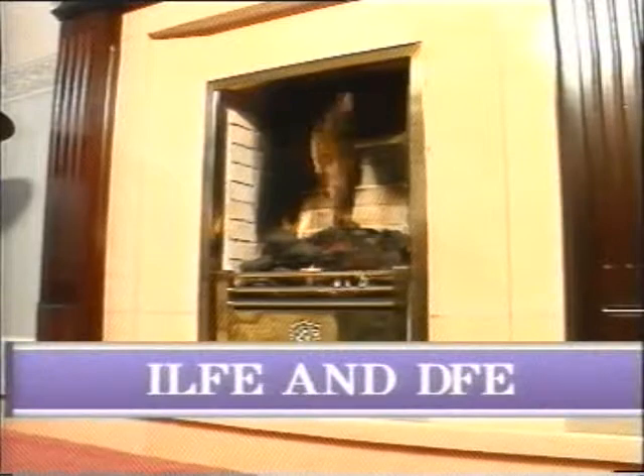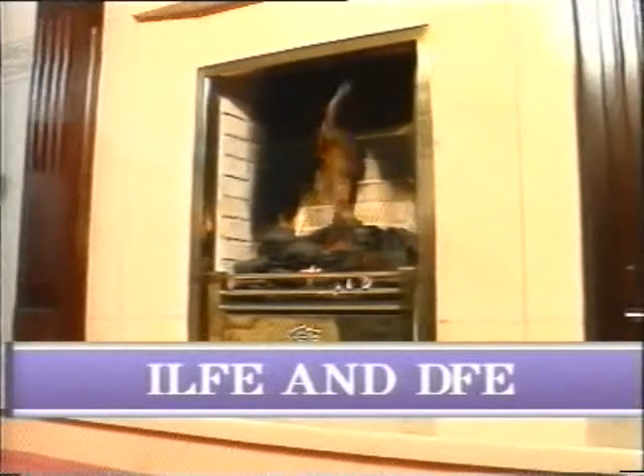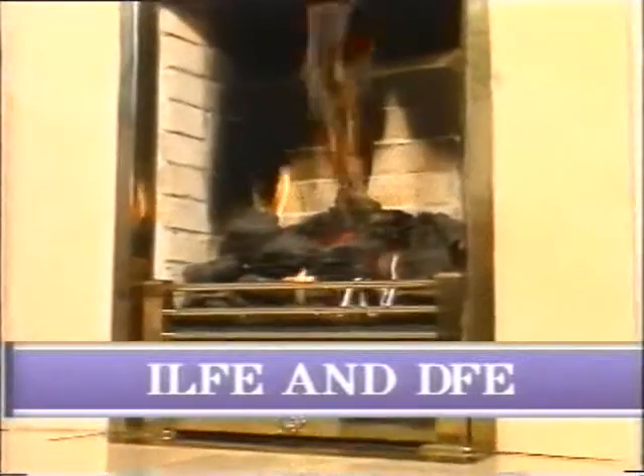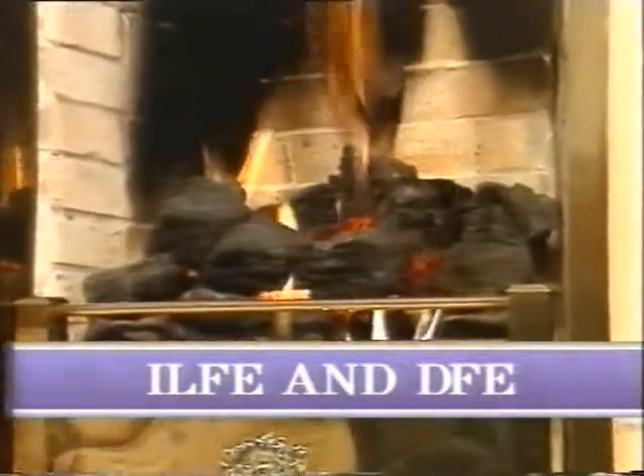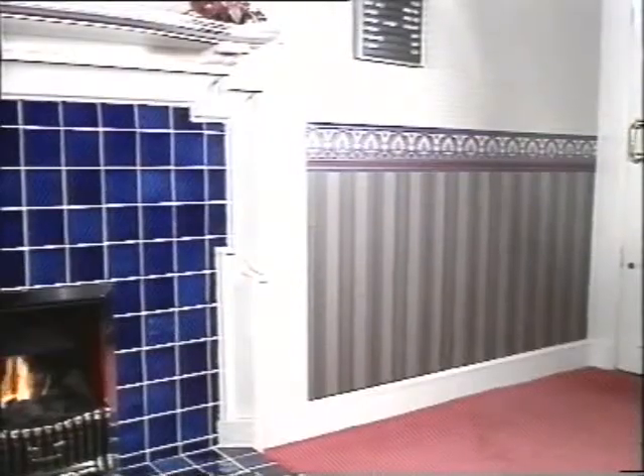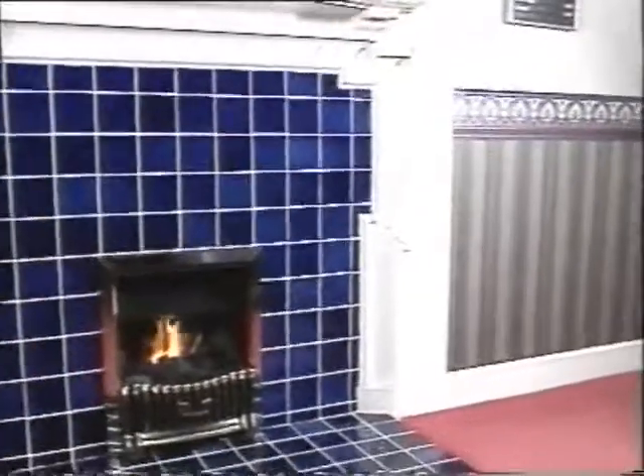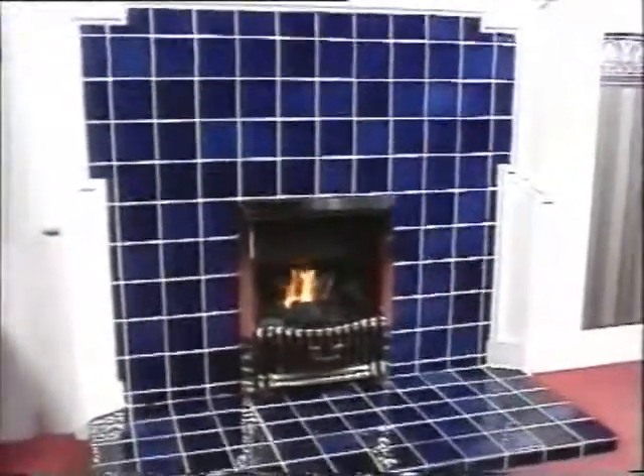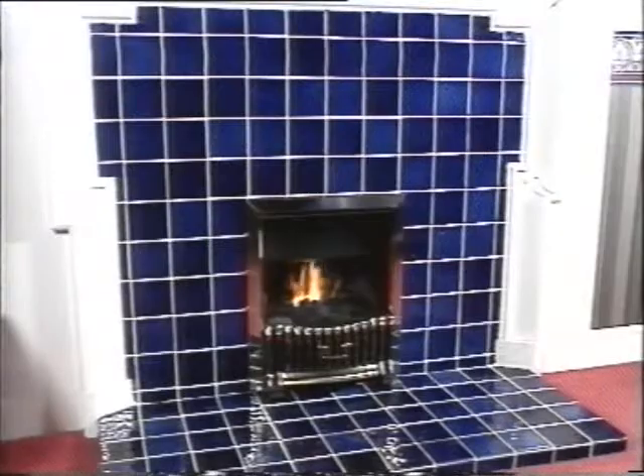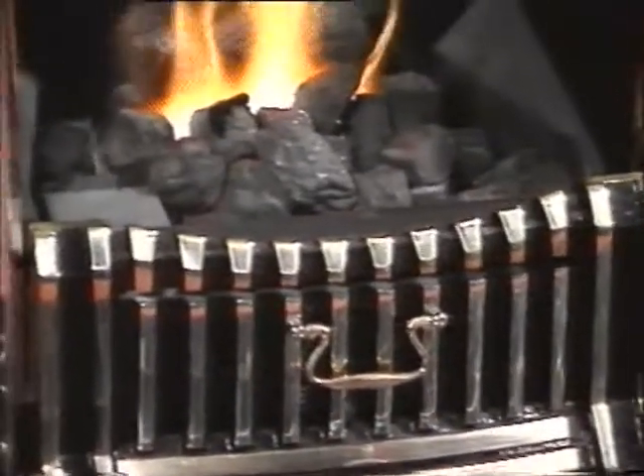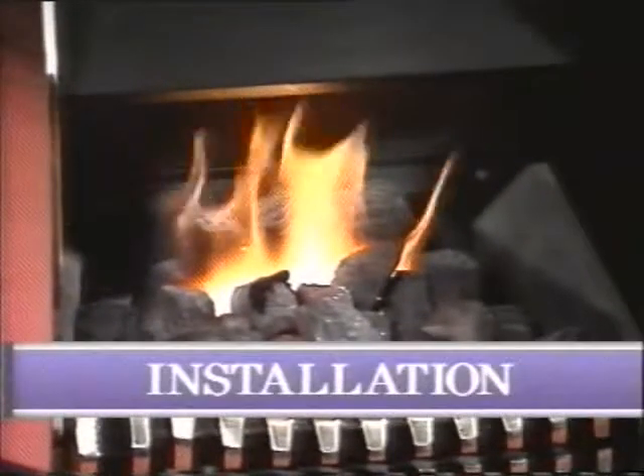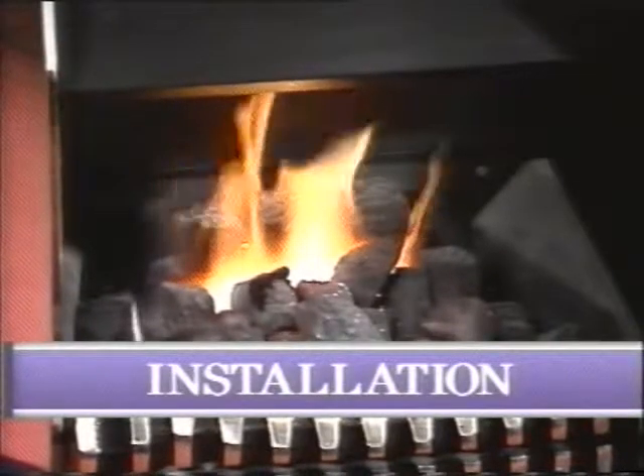These are known as insert live fuel effect, ILFE, and decorative fuel effect, DFE, appliances. The ILFE is in a heat exchanger box to convect heat into the room. The burner can be simplex, duplex, or of the sand tray type. Most of the rules about the siting of ILFEs are exactly the same as those which applied to radiant and convector fires. The rules for fire surrounds and the fireplace recess are the same too, but there's an additional requirement here.